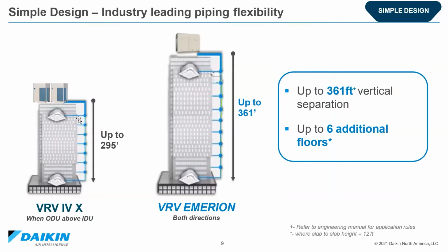With the new P-type compressor, the Emerion now has industry-leading piping capabilities. What used to be 295 feet of available vertical separation has now been increased up to 361 feet between the condensing unit and the fan coils. So for high-rise application, this could add up to 6 additional floors for a rooftop installation.